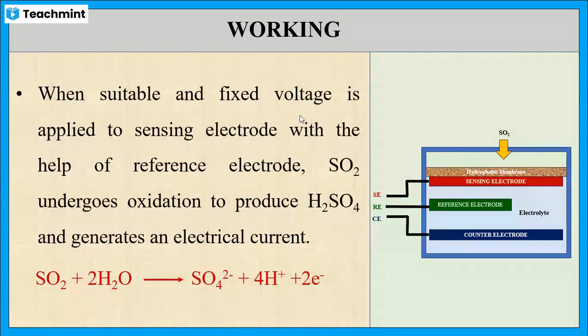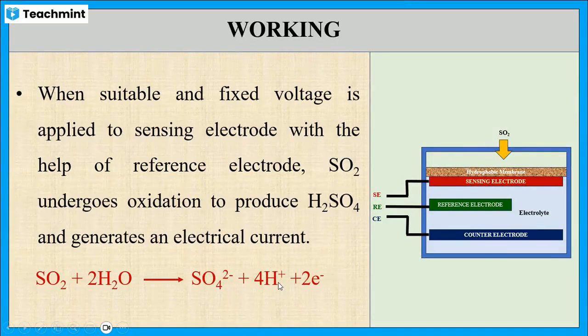So sulfur dioxide gets oxidized at the working electrode to produce sulfate ions and protons and generates an electrical current. This is the oxidation reaction where the electrons are liberated.